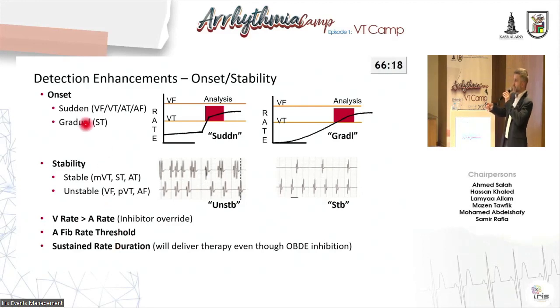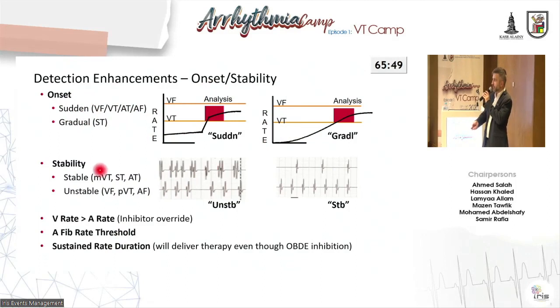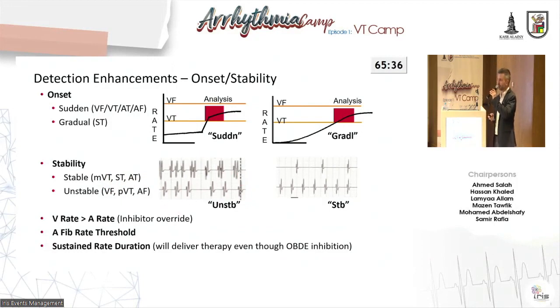Regarding onset and stability: if onset is sudden, the device interprets it as VF, VT, AT, or AF due to the sudden increase in heart rate. If gradual, the device interprets it as sinus tachycardia. For stability: if the rhythm is stable, it means monomorphic VT, sinus tachycardia, or atrial tachycardia. If unstable, it means VF, polymorphic VT, or AF.